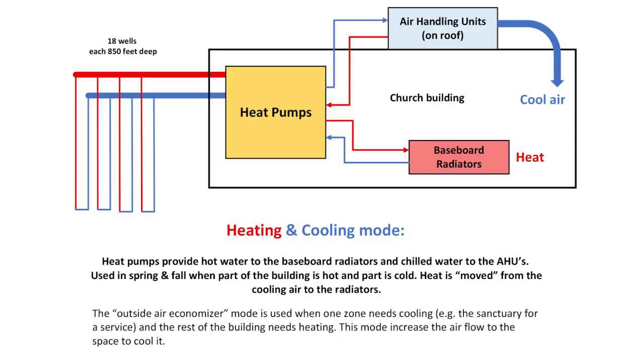The third and last mode is both heating and cooling, typically used in fall and spring. For example, in spring the north side of the building is shaded by trees and still cool, needing heat, while the south or west side gets direct sun and bakes those rooms. So we have to both heat some areas and cool other areas at the same time.